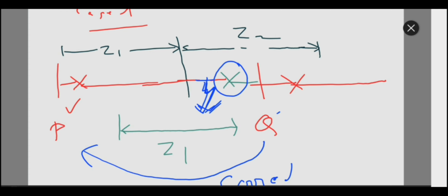So the system is protected in 0 seconds even if the fault occurs in zone 2 of the sending end relay. So I hope you understand the process and the meaning of the carrier signal. This type of protection is also called PUTT, that is permissive underreach transfer trip. Now let us understand case 3.